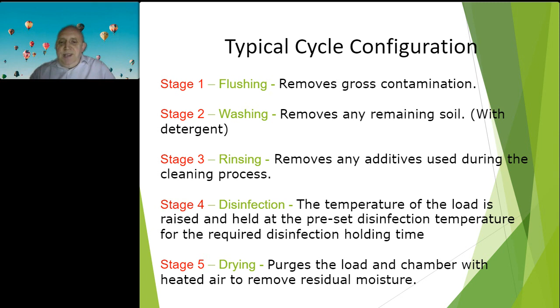This can differ dependent on application, but generally: flush to remove gross contamination, wash with detergent to remove any remaining soil. What types of detergent do you use? That will differ - is it the appropriate detergent? And what should we do if we're using detergent? Because if you think, we validate these washer disinfectors, any changes in detergent could impact on the water quality we have at source. We rinse to remove chemical additives. We disinfect - I mentioned earlier A0 of 600, which is a European figure we actually use, typically 90 degrees for 1 minute. And then we dry - highly important, we want a dry product prior to any packaging for sterilization.